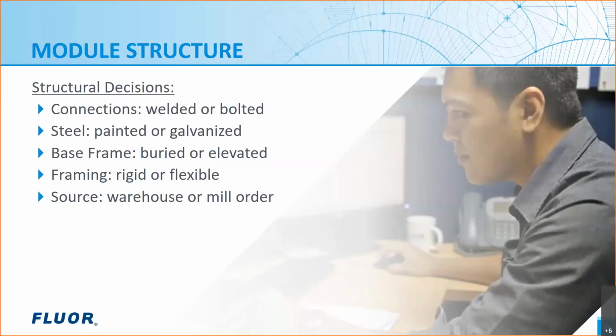Buried or elevated base frames. This is also a fundamental layout issue. Elevated base frames are more common due to simpler module setting requirements. Buried frames have more flexible egress alternatives and eliminate the need for operators to climb to the first level of equipment. Rigid or flexible framing. This is determined by the relative amount of bracing to be used. Modules may need to be rigid for crane lifts or to overcome transportation issues. Warehouse or mill order. In some global locations, quality is more assured by avoiding warehouse material.